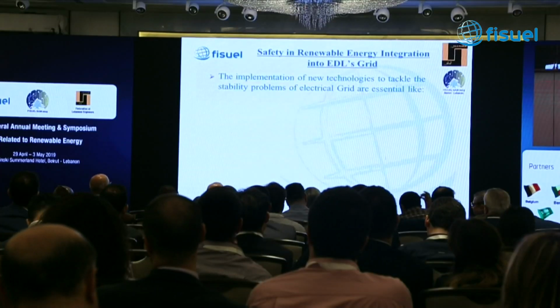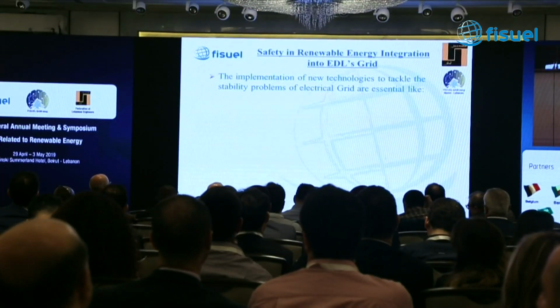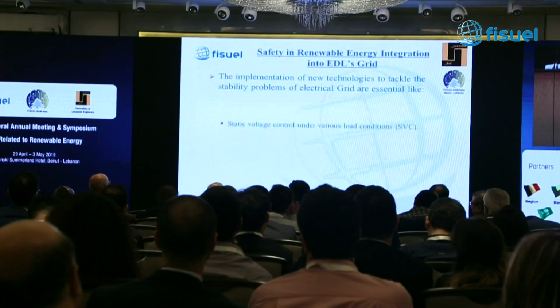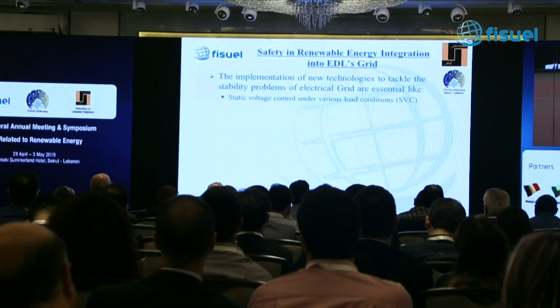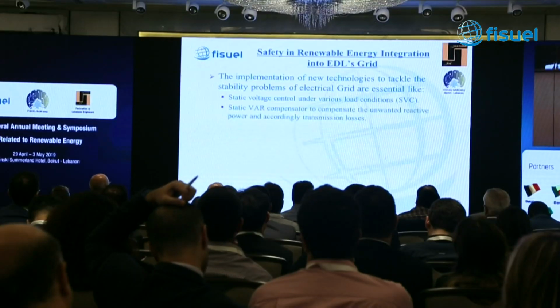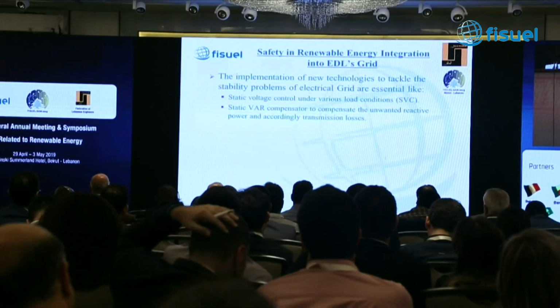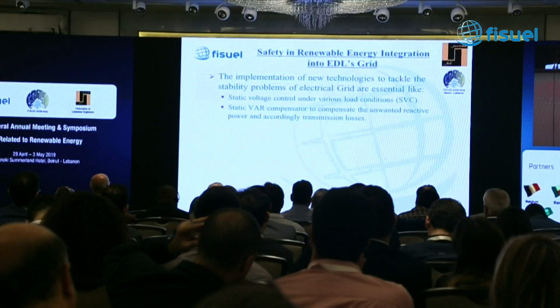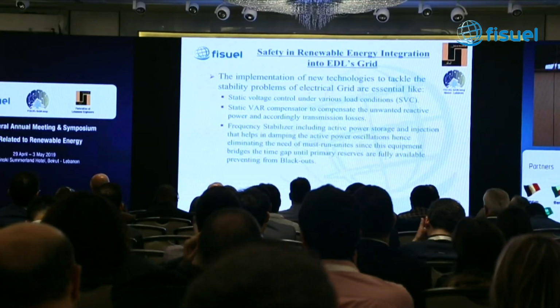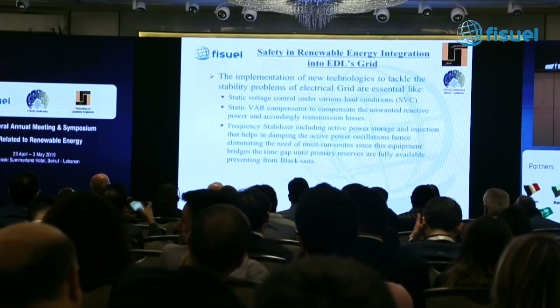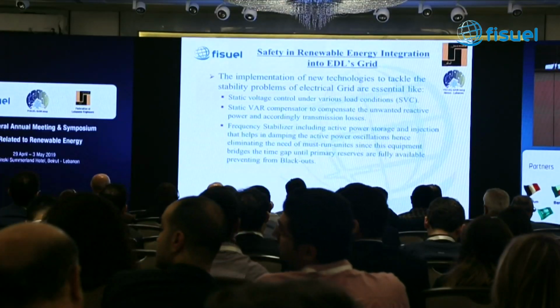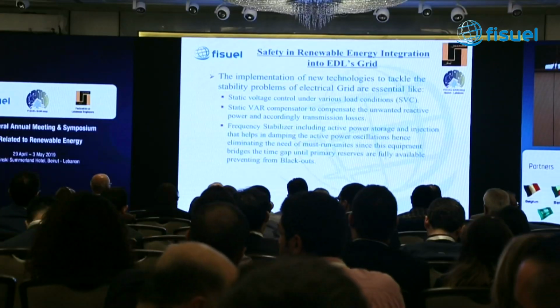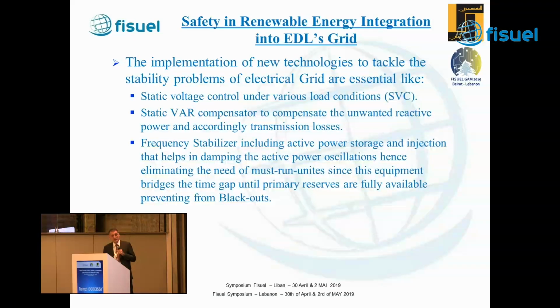Also, implementation of new technologies to tackle the stability problems of the electrical grid is essential, like installing static voltage controls under various load conditions, static VAR compensators to compensate unwanted reactive power and reduce transmission losses, and frequency stabilizers including active power storage and injection that help dampen active power oscillations, eliminating the need for must-run units, since this equipment bridges the time gap until primary reserves are fully available, preventing blackouts.